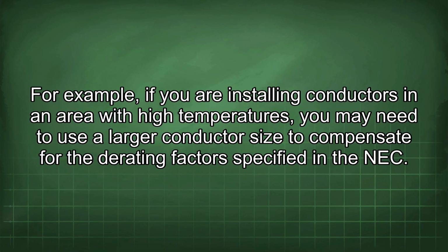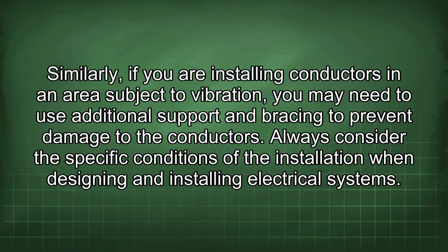For example, if you are installing conductors in an area with high temperatures, you may need to use a larger conductor size to compensate for the derating factors specified in the NEC. Similarly, if you are installing conductors in an area subject to vibration, you may need to use additional support and bracing to prevent damage to the conductors. Always consider the specific conditions of the installation when designing and installing electrical systems.